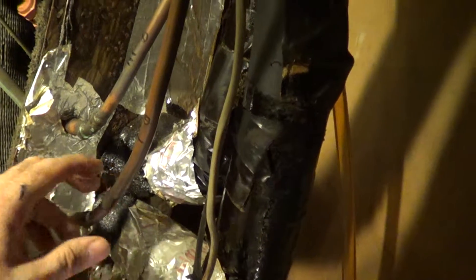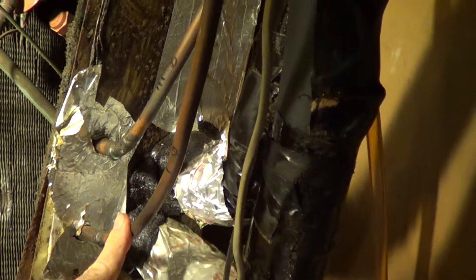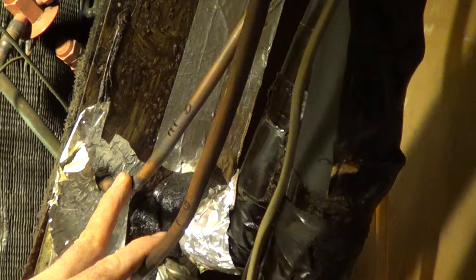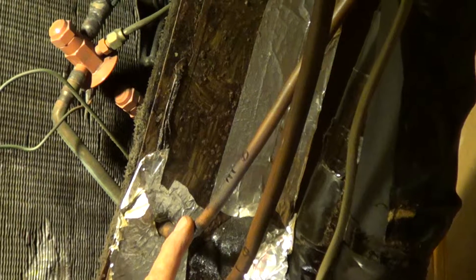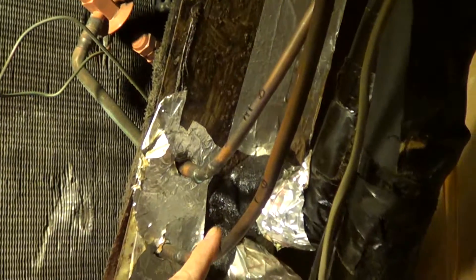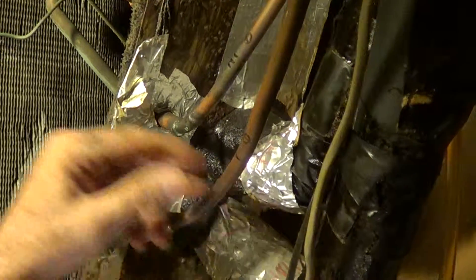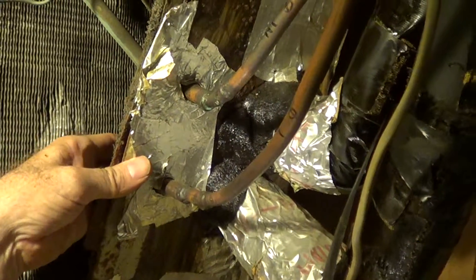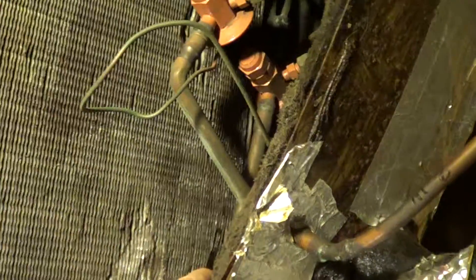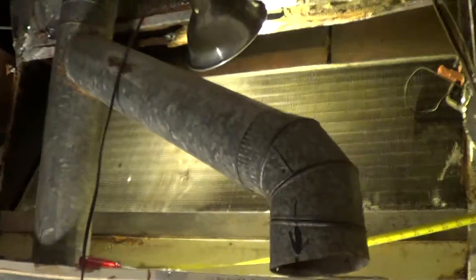I'm going to have to charge this with some nitrogen and a tad of R22 to find the leak. The three-phase unit from 1985 has an EER of around 8.5 — that's a Carrier round 5-ton unit. On the single-phase line there's a Rheem 10-ton unit, and when it was installed this line would vibrate all the time, so there's probably a fatigue failure. Hopefully it's right at the connection, but it might be back in the coil.